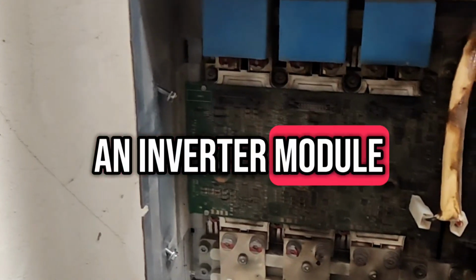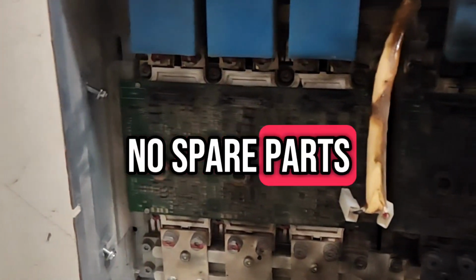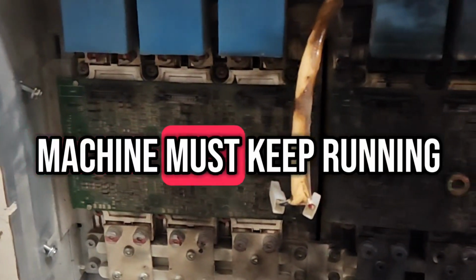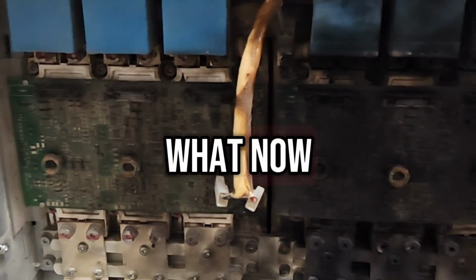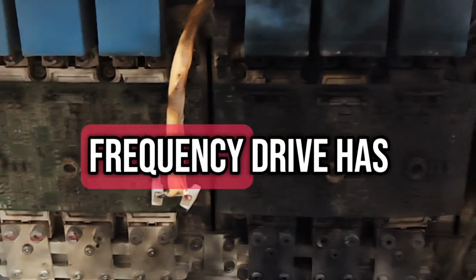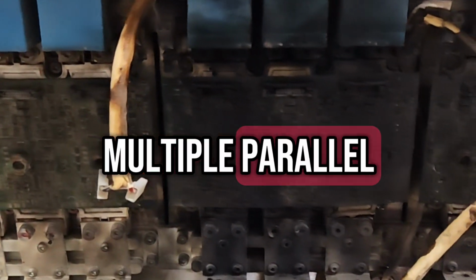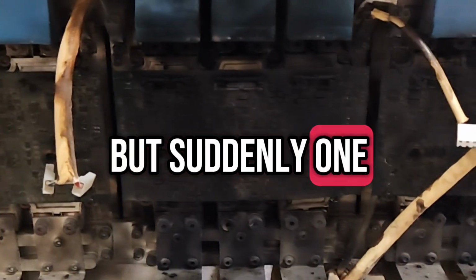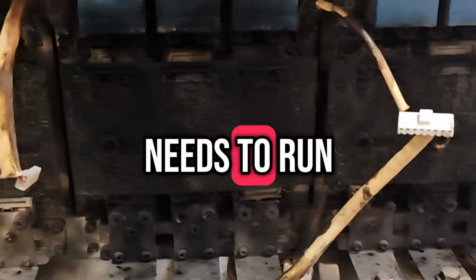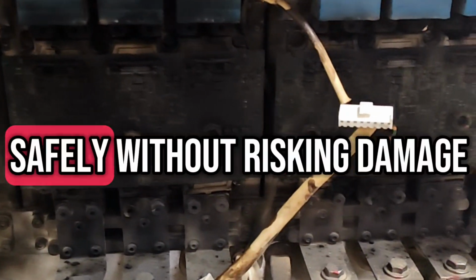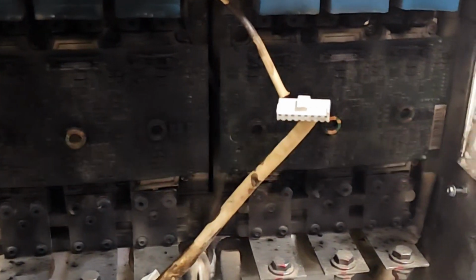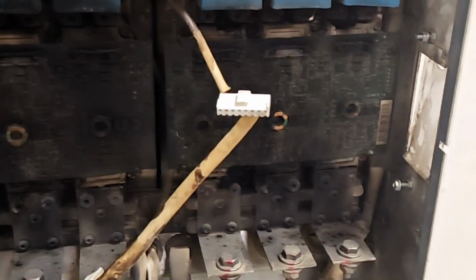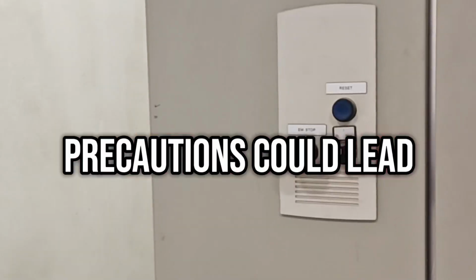An inverter module is down. No spare parts in sight. The machine must keep running. What now? Your ABB variable frequency drive has multiple parallel inverter modules, but suddenly one fails. The equipment needs to run, but how do you do it safely without risking damage? Stopping production isn't an option, but running without precautions could lead to disaster.